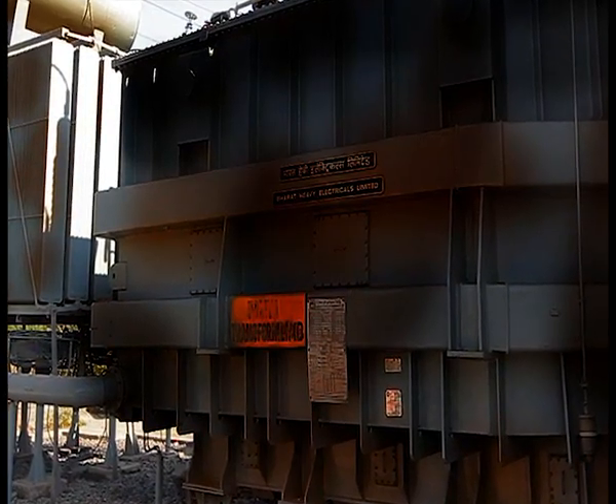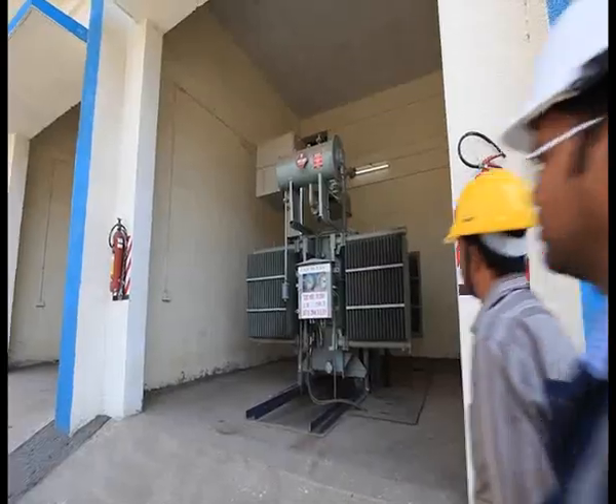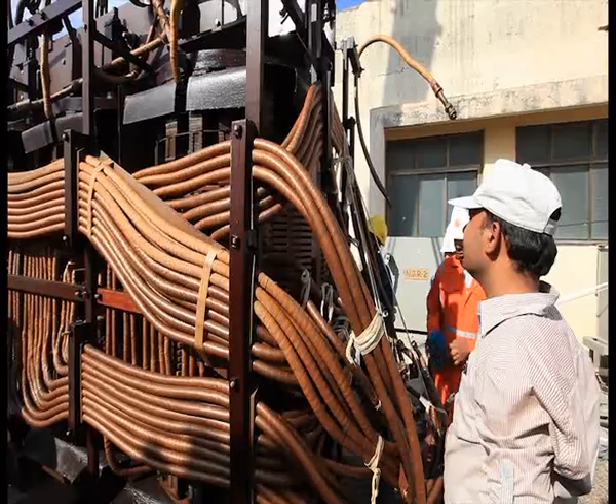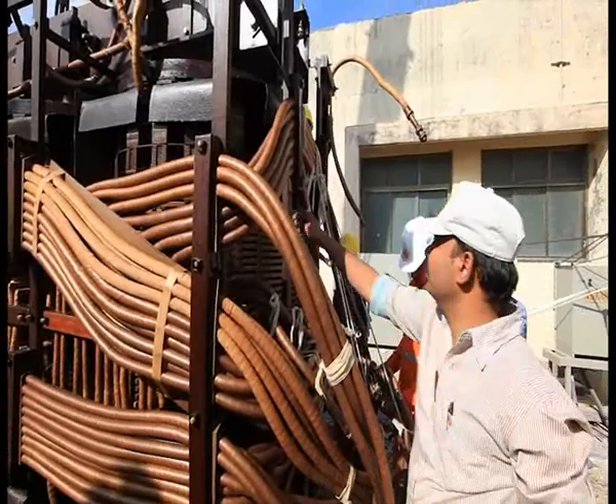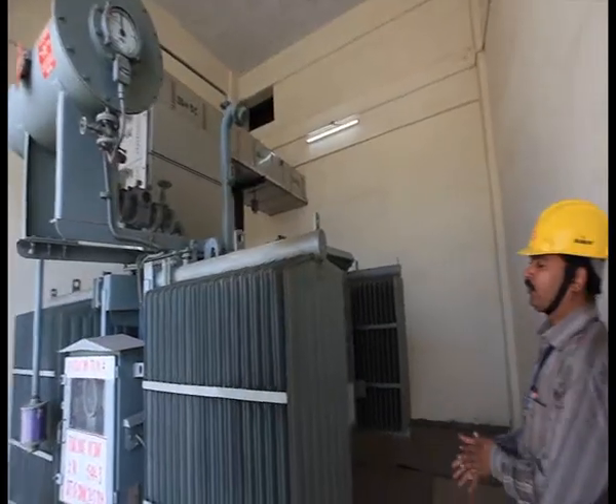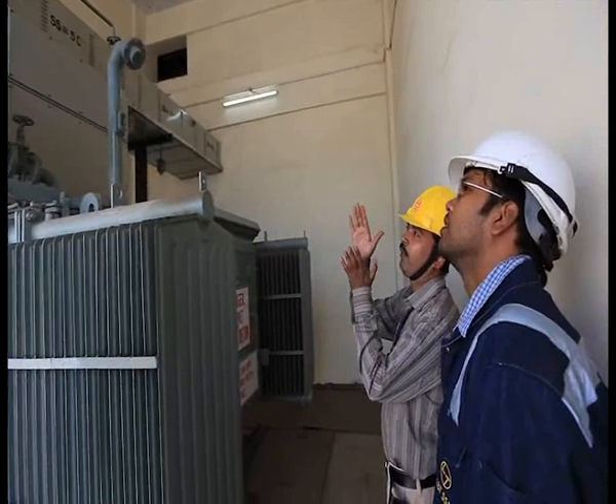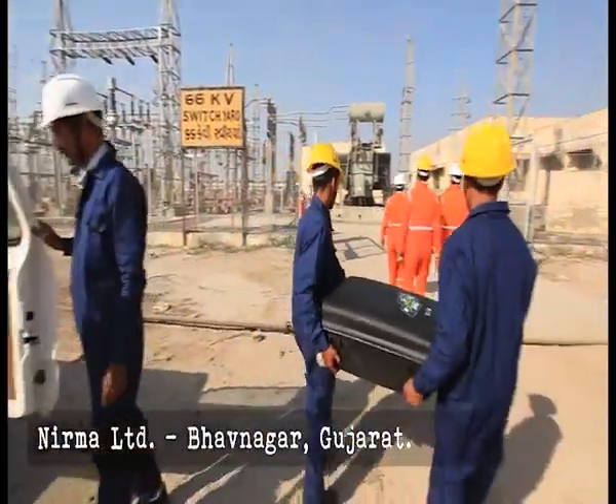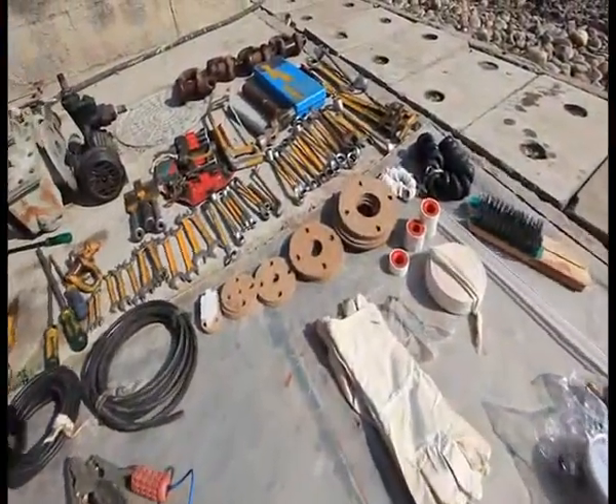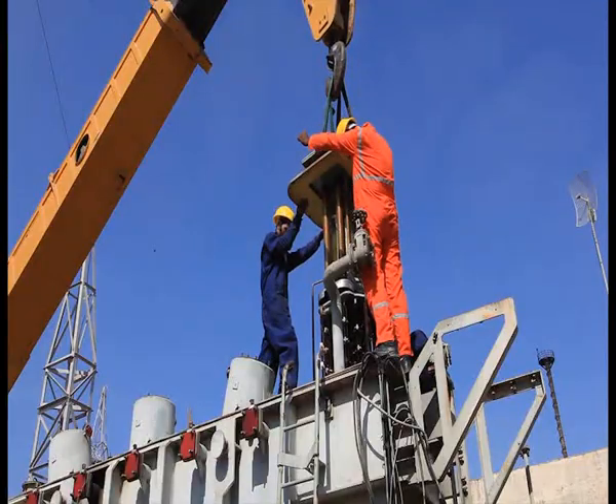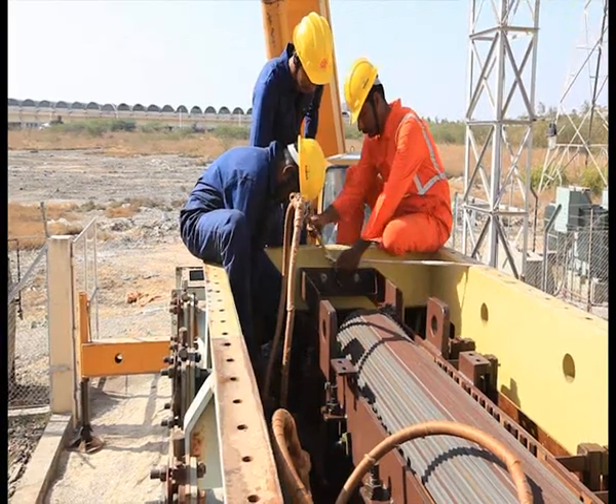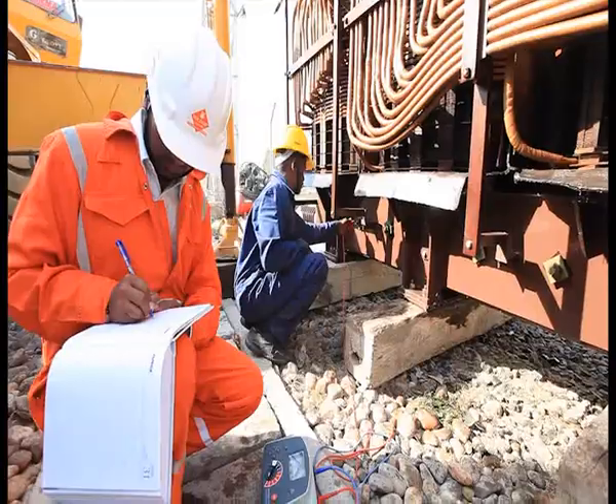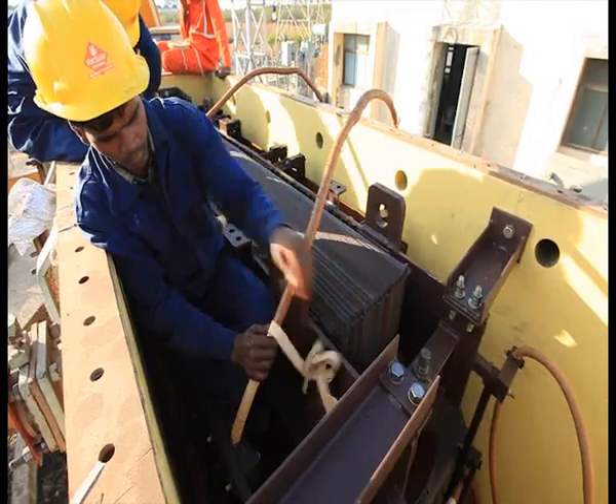In the event of a failed or damaged transformer, you just have to call the nearest SAS service center. Our technical person will reach the site in 24 to 48 hours, depending upon the site location. We'll assess the situation and give you a rough estimate of the cost and time involved in rectifying the problem. A technical workforce with the necessary tools, testing equipment and spare parts reaches the site immediately. If the client provides lifting and handling facilities, a closed area with an EOT crane and working space, then the transformer is rectified on site.